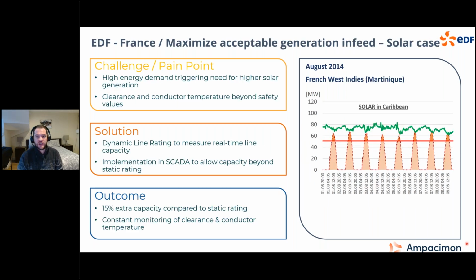But that's not the only case. This example is EDF in France, same idea but with a solar plant. Every day when the sun shines it hits a maximum, and on particularly sunny summer days it would exceed the static rating. By including DLR, they could run it at full output without any curtailment, giving a good solid 15% extra capacity - enough to justify the project.